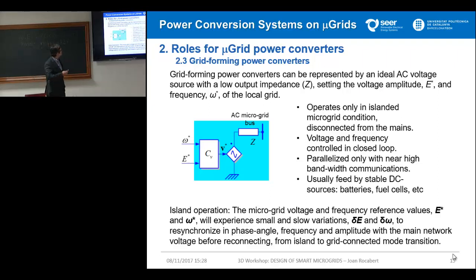Also, this grid forming converter is able to work only in island mode, because we cannot get two voltage sources connected between them, as it's a very unstable condition, unless the impedance is big enough to maintain stability. If this impedance is very small, you are going to get a lot of problems with stability.